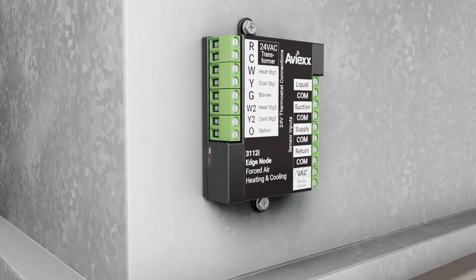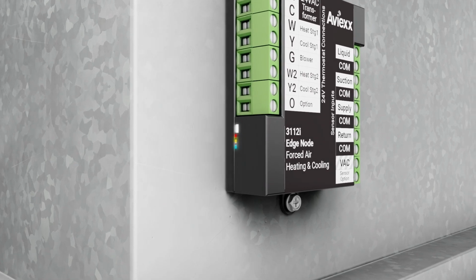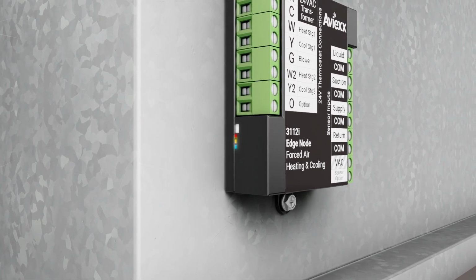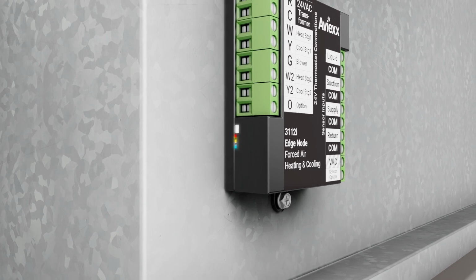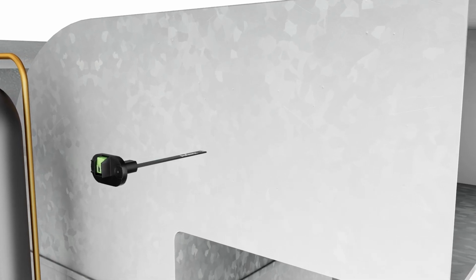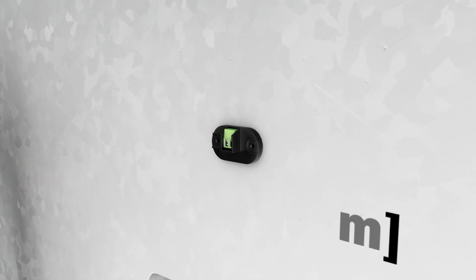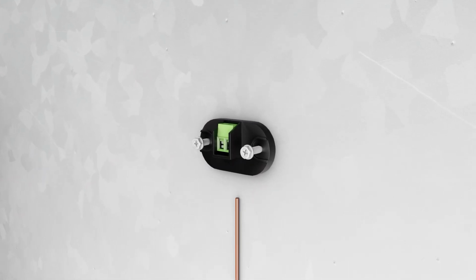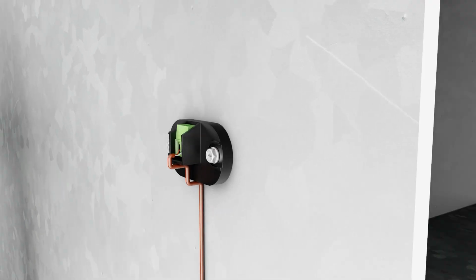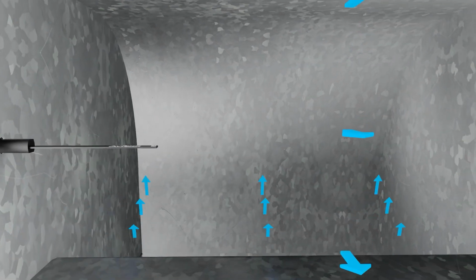Ideally, the indicator LEDs should be easily visible after the device is completely installed. This will come in useful later. Mount air temperature sensors by drilling a 5/16 inch hole in the sheet metal.